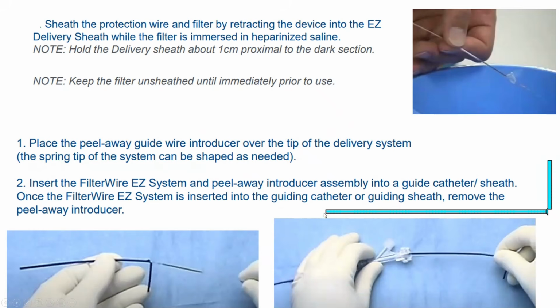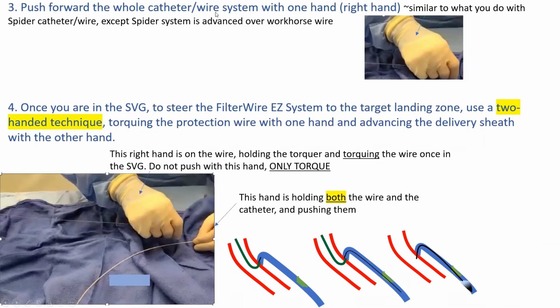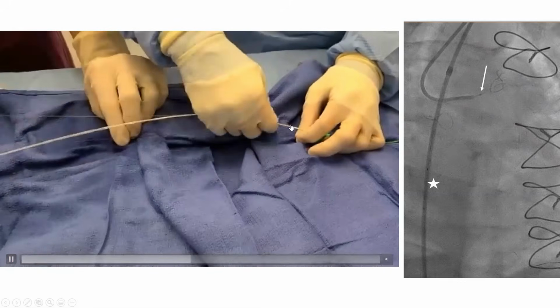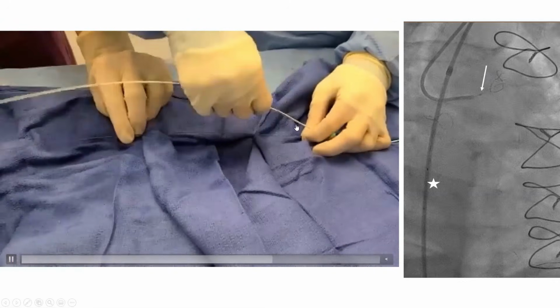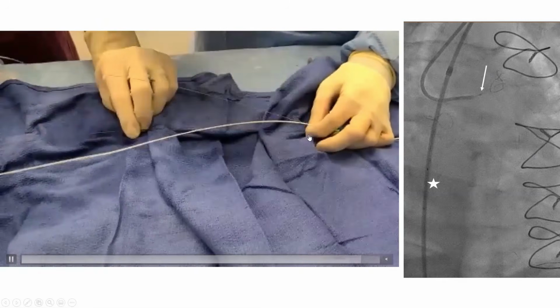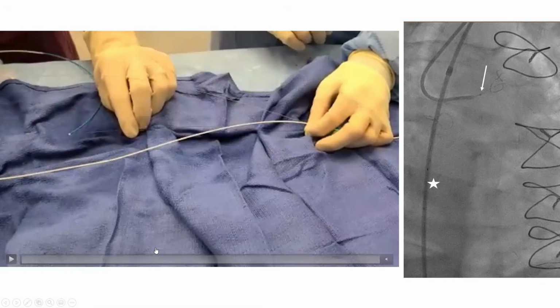So you use a peel away plastic that you put your wire and catheter through, and you put that through the Y-adapter, and then you push the system. And once your filter wire is around here in the guiding catheter, then you remove that peel away plastic. Then you push the whole catheter wire system with one hand, the right hand, kind of similar to what you do with a Spider catheter wire, except with a Spider wire, it is advanced over a workhorse wire. So like here, you're pushing both the filter wire and catheter together, except unlike with a Spider, you don't have a buddy wire. You're just pushing the other two with one hand.